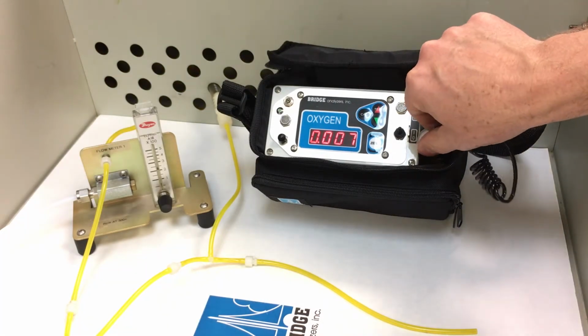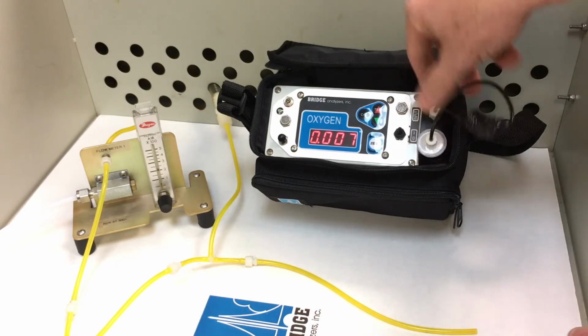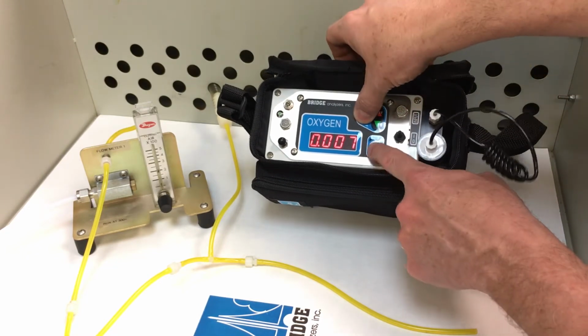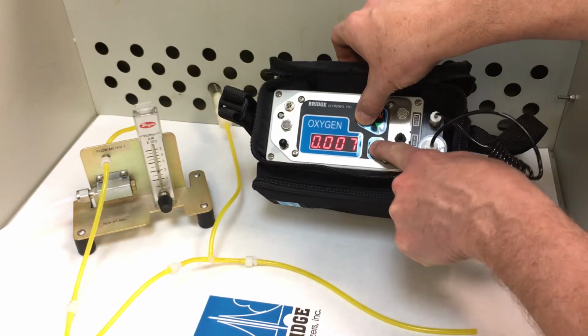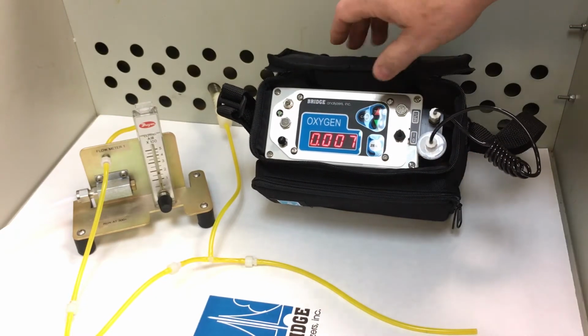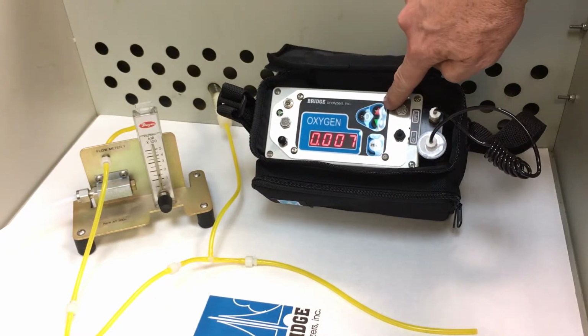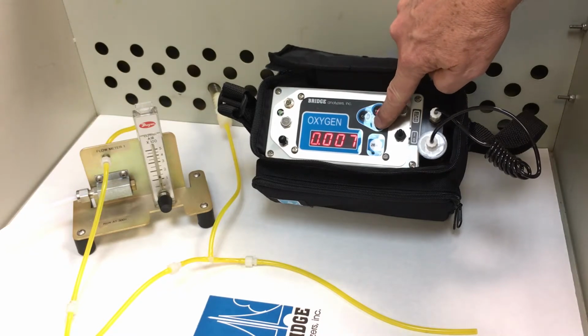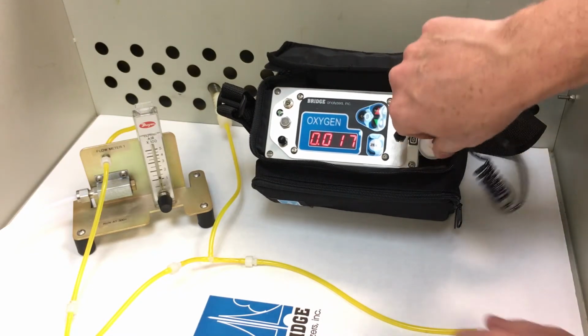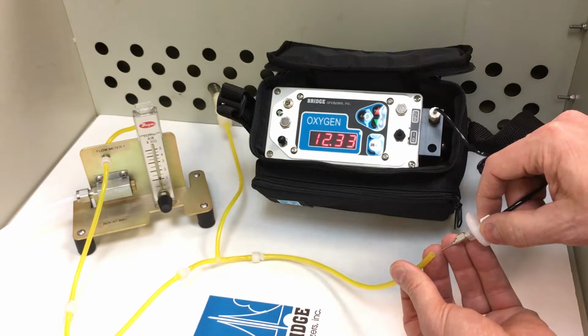The one thing I didn't show you was if you're in the calibration mode, right now, watch. I try to go into calibration mode. I can't get in there. Well, I can't get in because I'm in the test and hold mode. So if I just hit that green arrow, I go back to continuous testing.